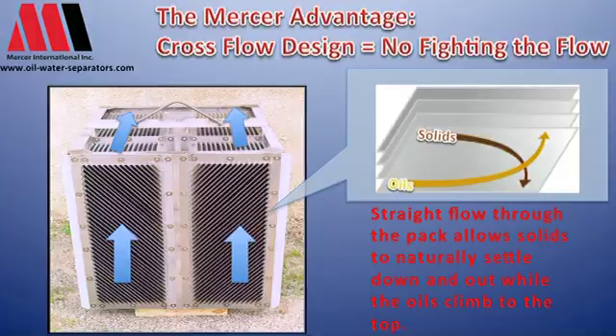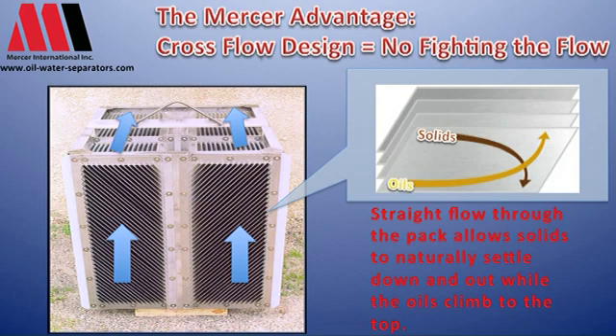On the better designs, like on the Mercer design, you'll see that it's a cross flow. Here, you have flow coming in in this direction. Solids drop in generally the same direction as the flow. Oils come up and out in generally the same direction. And therefore, you have a cross flow design.